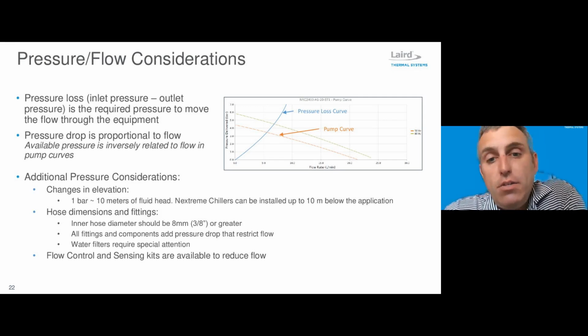So in this case, on the chart example on the right, you can see the blue line. As the flow increases, so does the pressure. It's exponential, with a square relationship. But the thing to notice here is that the pump curve, just like a fan curve, is inversely related to the flow, the pressure and flow are. And so as the required flow goes up, the pressure decreases.